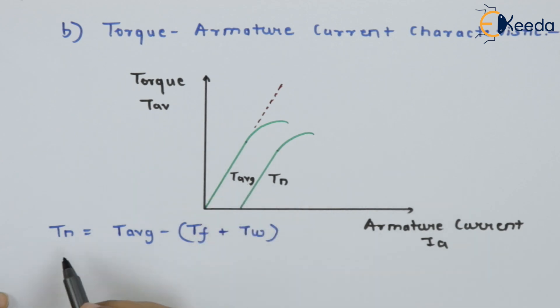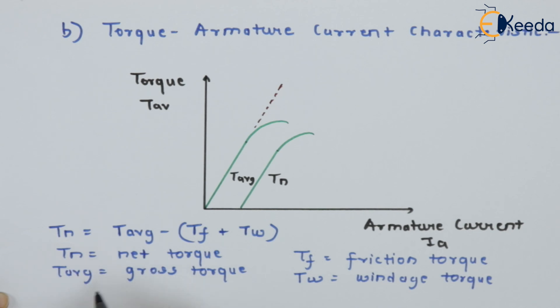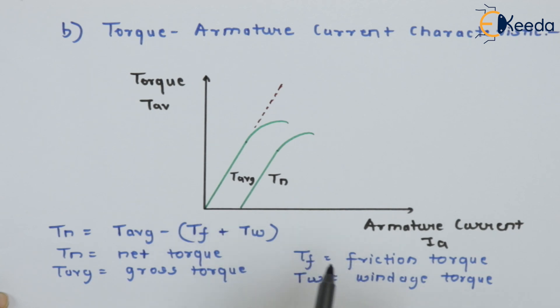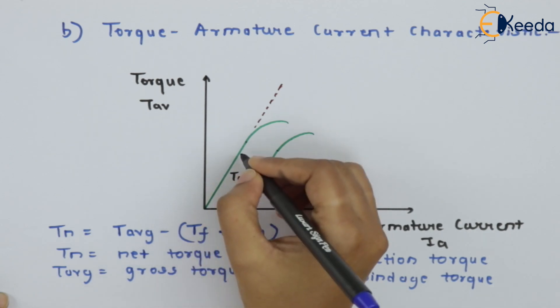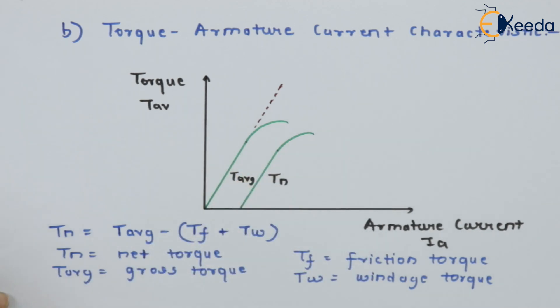For low values of current, that is at no-load condition, we have assumed flux as constant. Hence, the characteristic of torque versus armature current is a straight line. But at higher values of current, that is when the load goes on increasing, the effect of armature reaction is seen on the torque, and the torque slightly goes on decreasing.